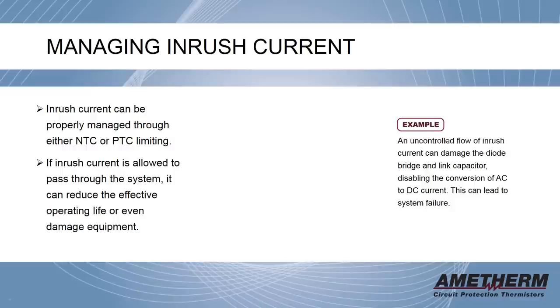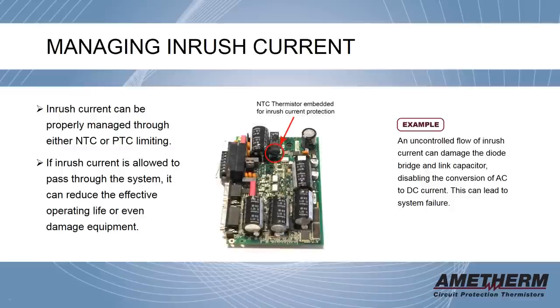Let's look at an example. As you can see in the photo here, an NTC thermistor has been embedded for inrush current protection. Without this thermistor, an uncontrolled flow of inrush current can damage the diode bridge and link capacitor, disabling the conversion of AC to DC current. This can lead to system failure.